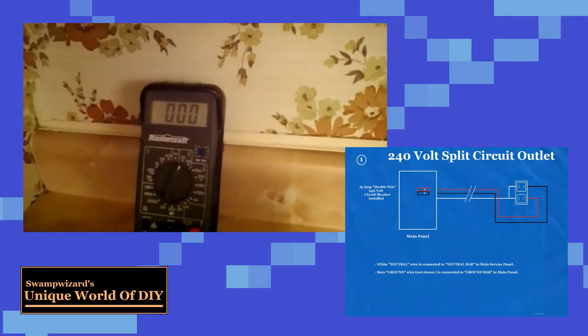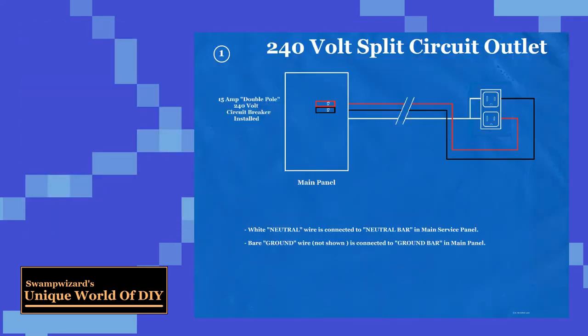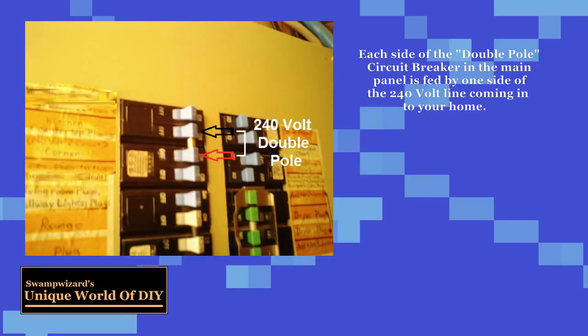You'll find them in kitchens, usually on the countertops. They run on a 15 amp double pole breaker. It's a 240 volt breaker. Now, depending, of course, if the building was wired to code or not, you never know, somebody may have come along and done something later on.